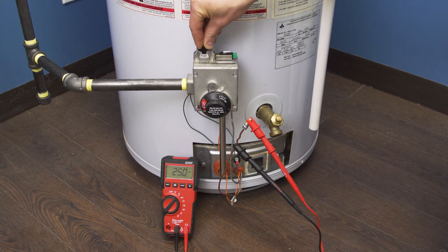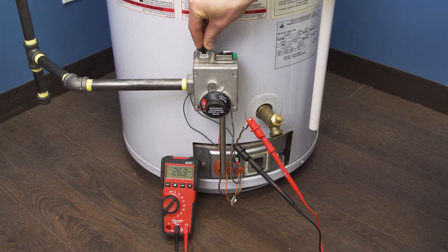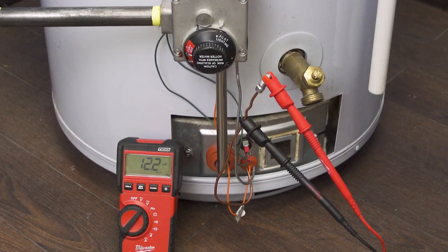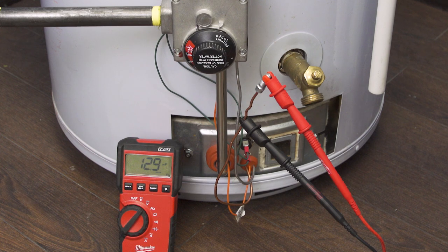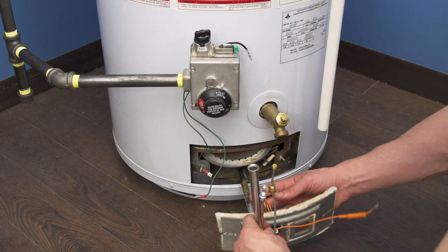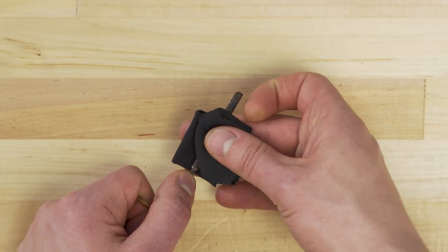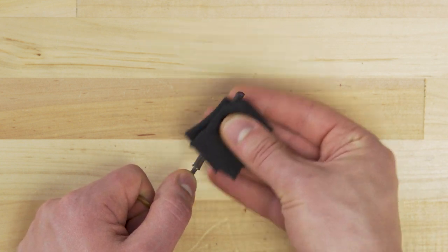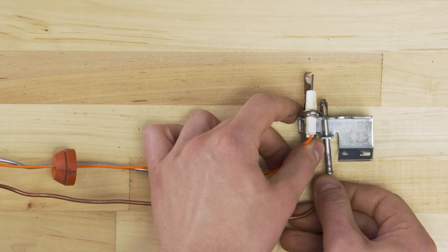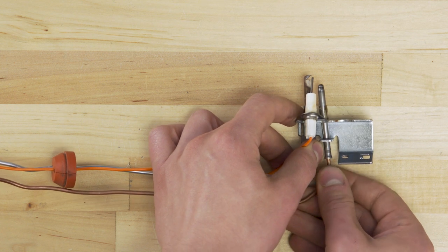In an open circuit test, a healthy thermocouple should read between 20 and 30 millivolts. If the multimeter reads under 20 millivolts, then the pilot might have trouble staying lit. Over time a buildup of carbon will act as an insulator and will reduce the voltage. One solution is to clean it, but in a lot of cases it's best to install a new thermocouple.